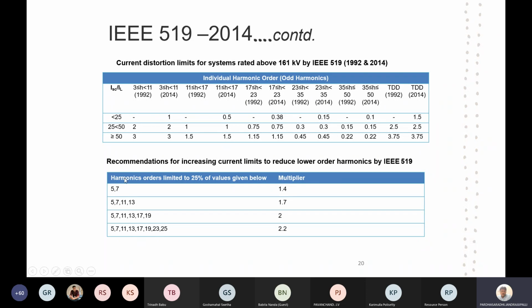So by seeing the above results, the recommendation is increasing current limits to reduce lower order harmonics. We need a multiplier to mitigate harmonic orders, limited to 25% of the value given below. When you consider this multiplier, like 1.4, 1.7, 2 and 2.2, the harmonic orders can be limited.